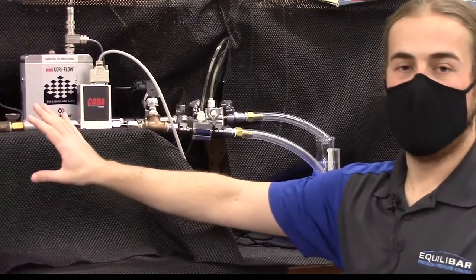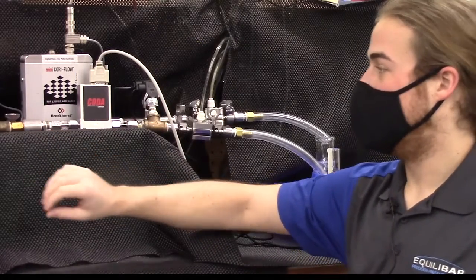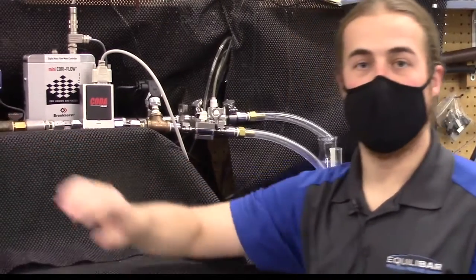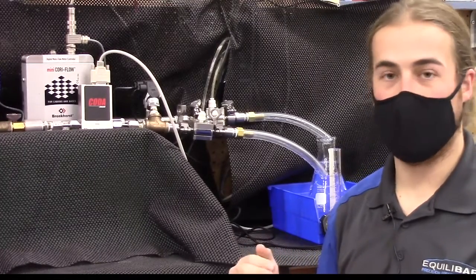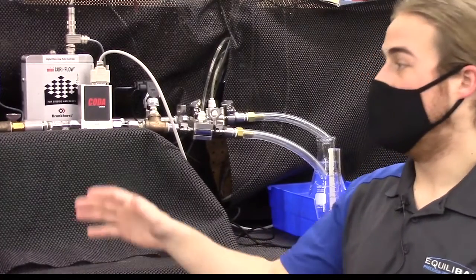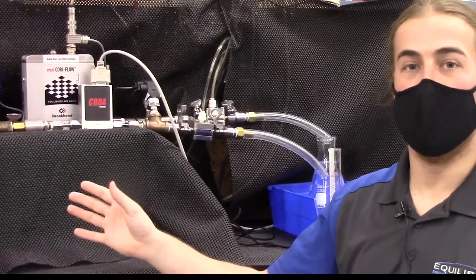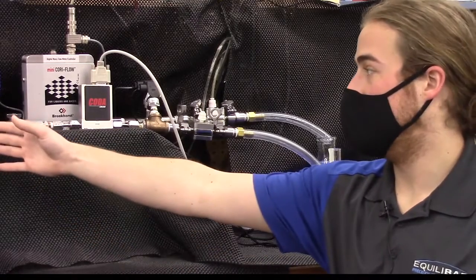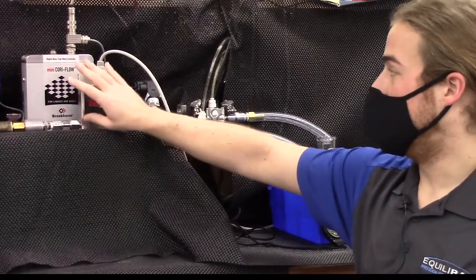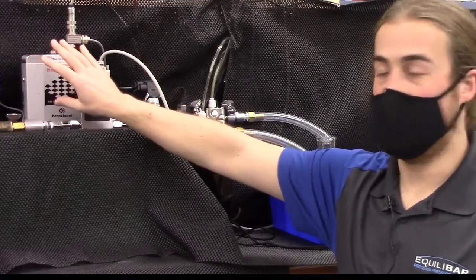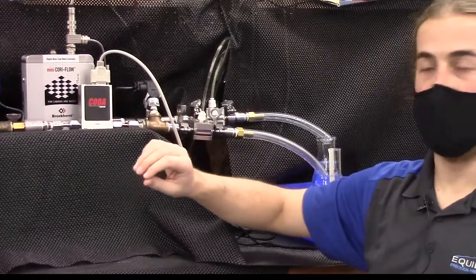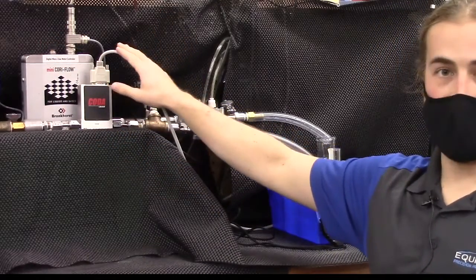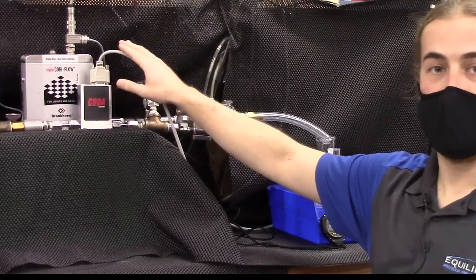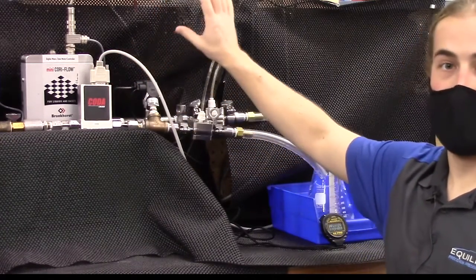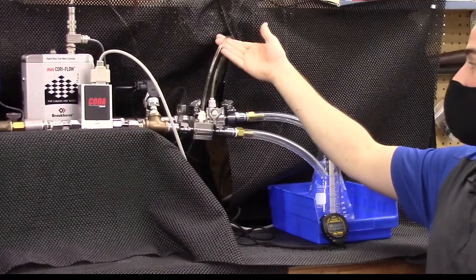So here is our setup in the lab. Just like the schematic here, we have two independent lines that are being supplied by head pressure-driven flow systems. In this case, we're supplying roughly 15 psi to our upstream side here.